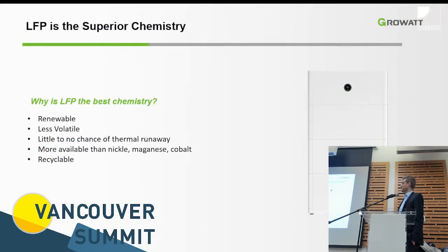The battery system is also quite nice because it's a stackable system. So you have 2 components. You have the battery management system with all the contactors, all the wiring terminals, everything built into one top unit. And then you have multiple battery modules that are stacked on a bottom tray. And each battery module is 5 kilowatt hours.